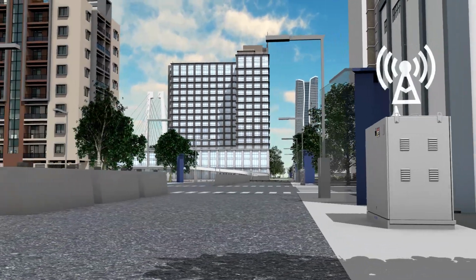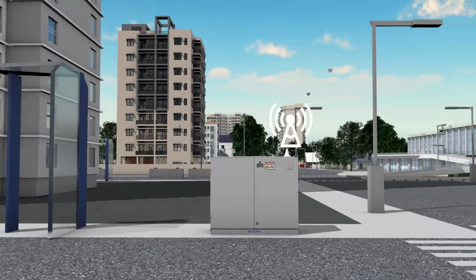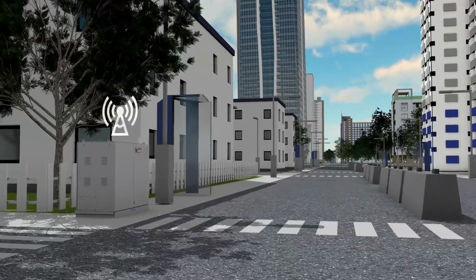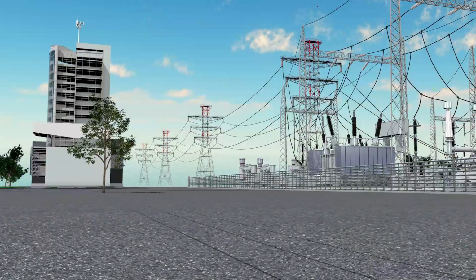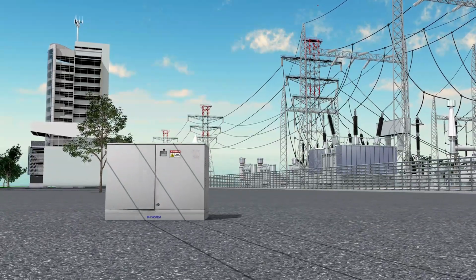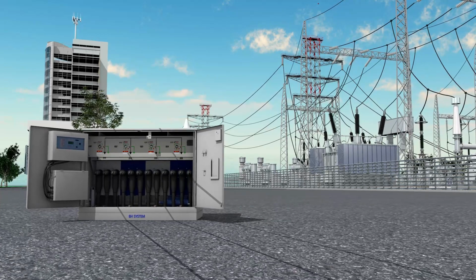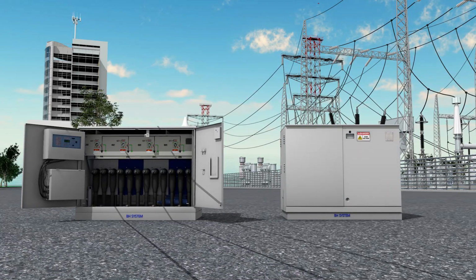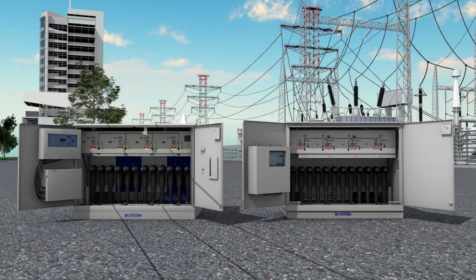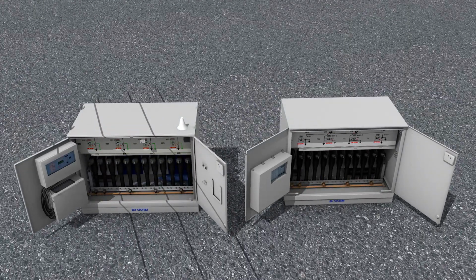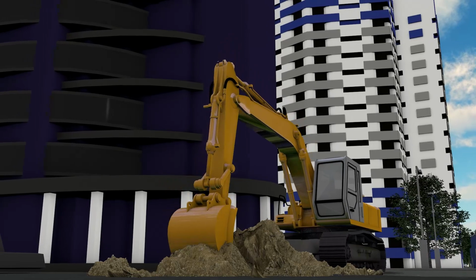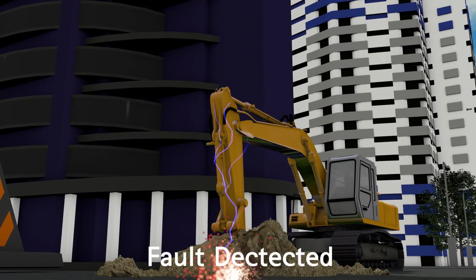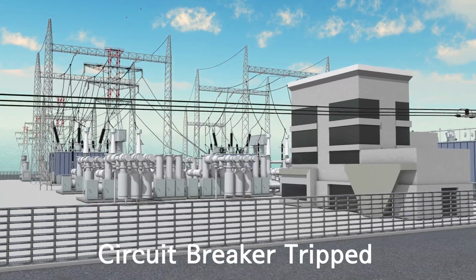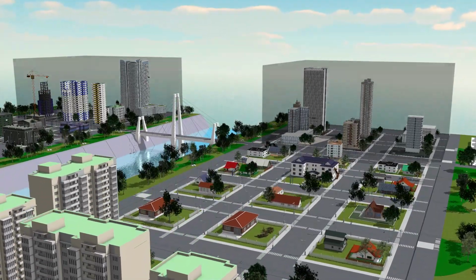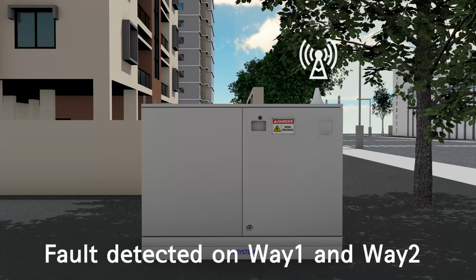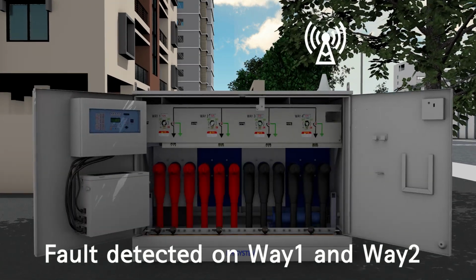The next animation shows how each product operates in the case of faults of the underground distribution line. Pad mount load break switches are used for line branch or sectionalization. Pad mount switchgears are used to prevent faults from spreading to the entire system by blocking faults on the customer service line. When the circuit breaker in the substation operates against a fault on the line, the entire line will be blacked out and load break switches on the line will detect the fault or the loss of all potential. And this information will be transmitted to the Distribution Control Center.